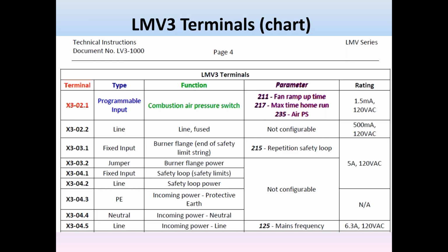211 gives you time that you need to break the air pressure switch, so that when a fan starts, you can do your fan run-up time and give yourself 2 or 3 or 10 seconds, whatever it takes to make the air pressure switch. And then 217 is when you shut down the fan, gives you time to let the air pressure switch open, so you don't get a fault saying that there's a stuck air pressure switch on shutdown. 235 is an additional parameter, so you can use and decide what phases the air pressure would be measured in.